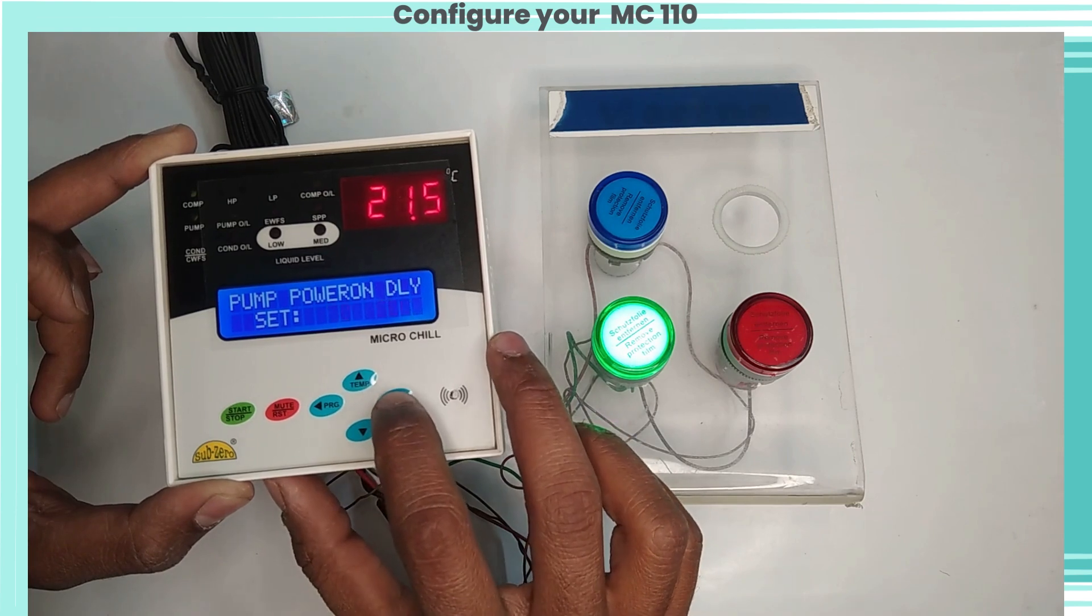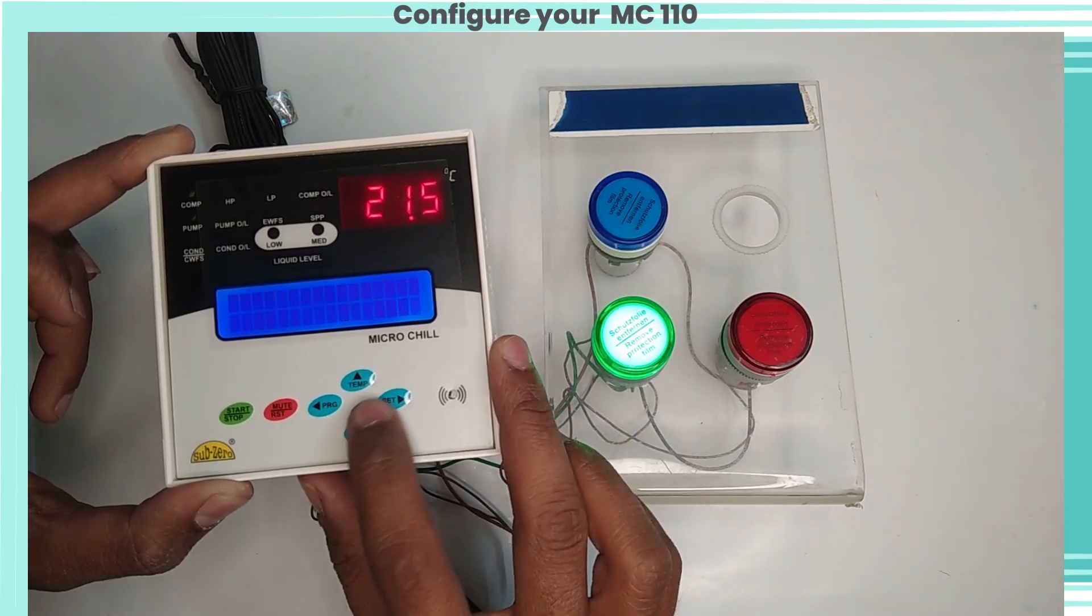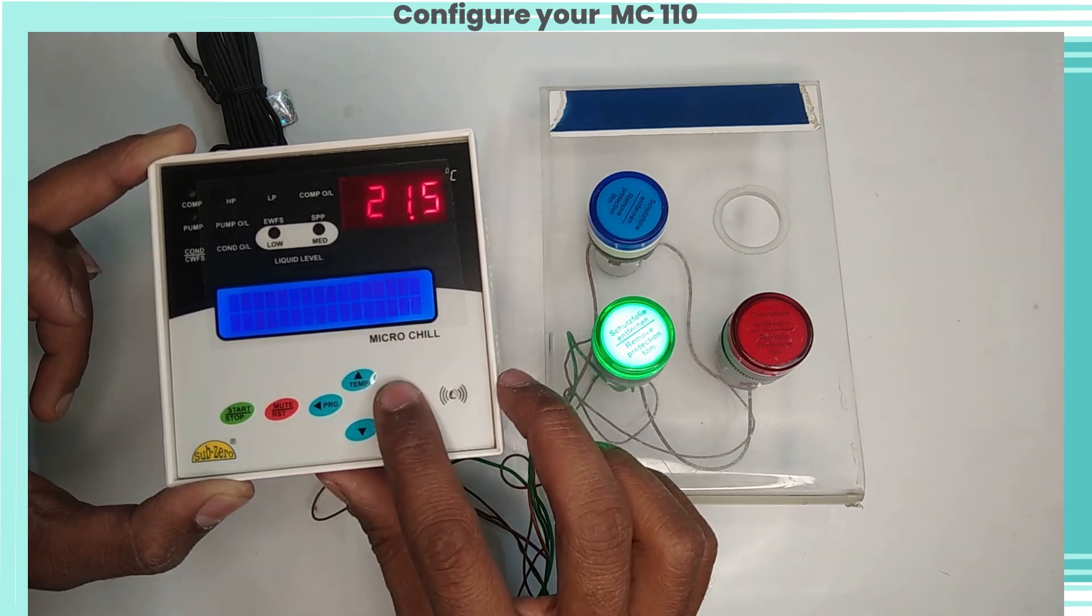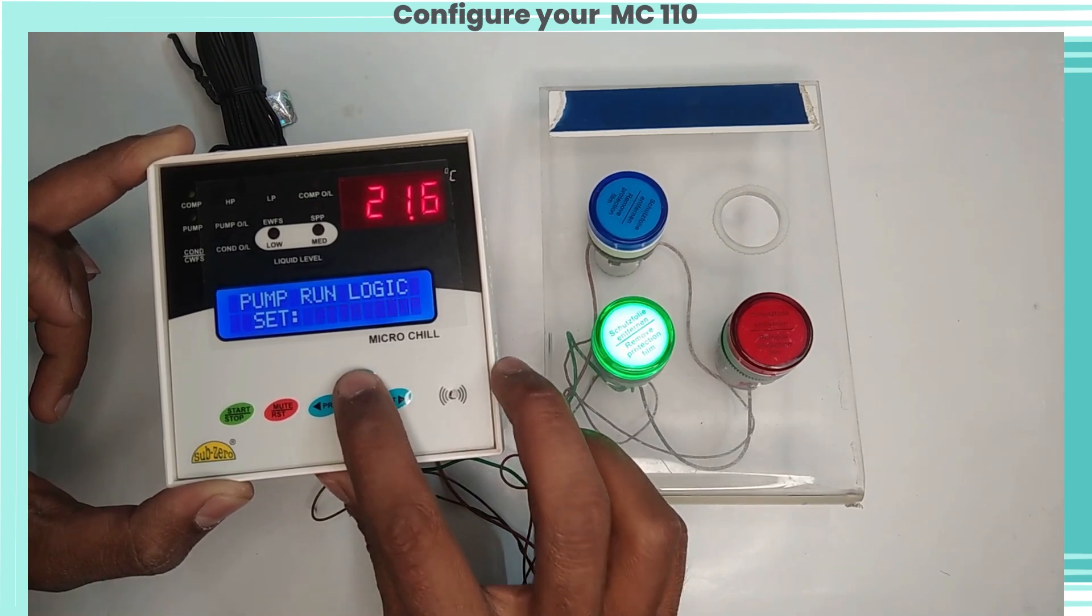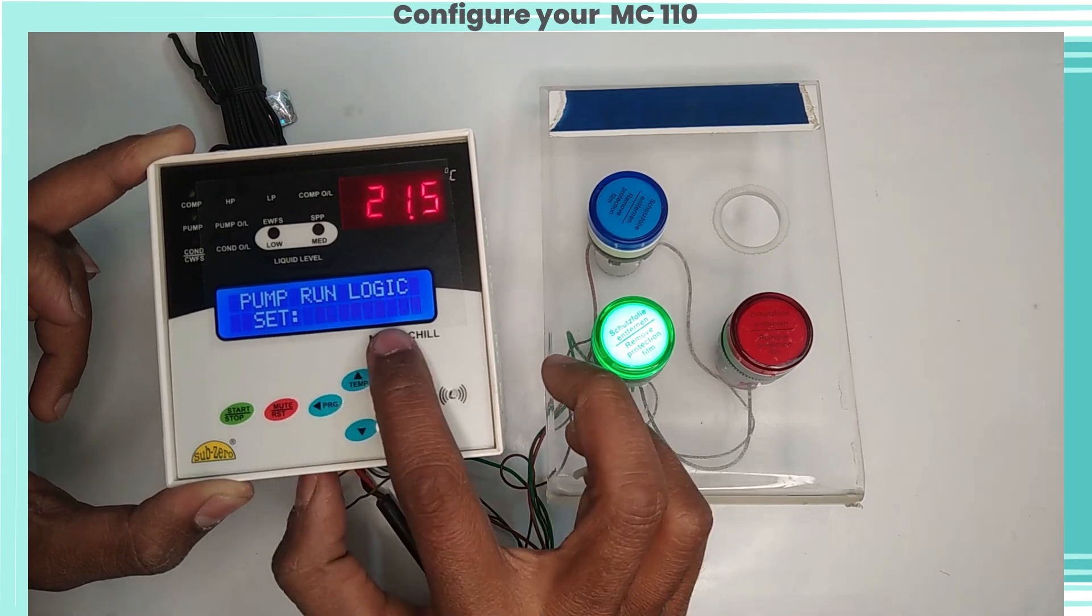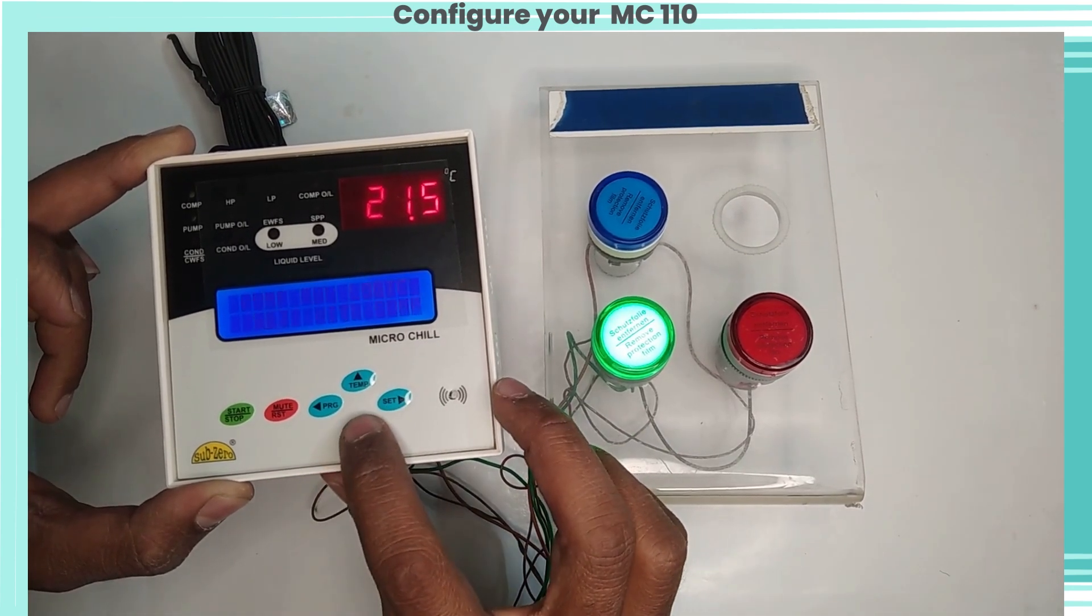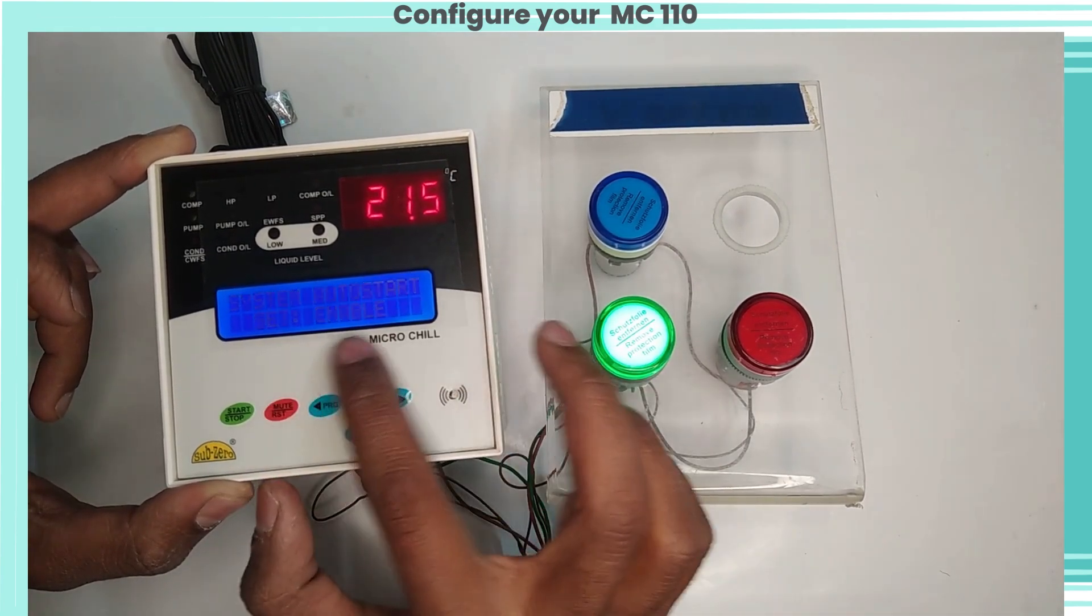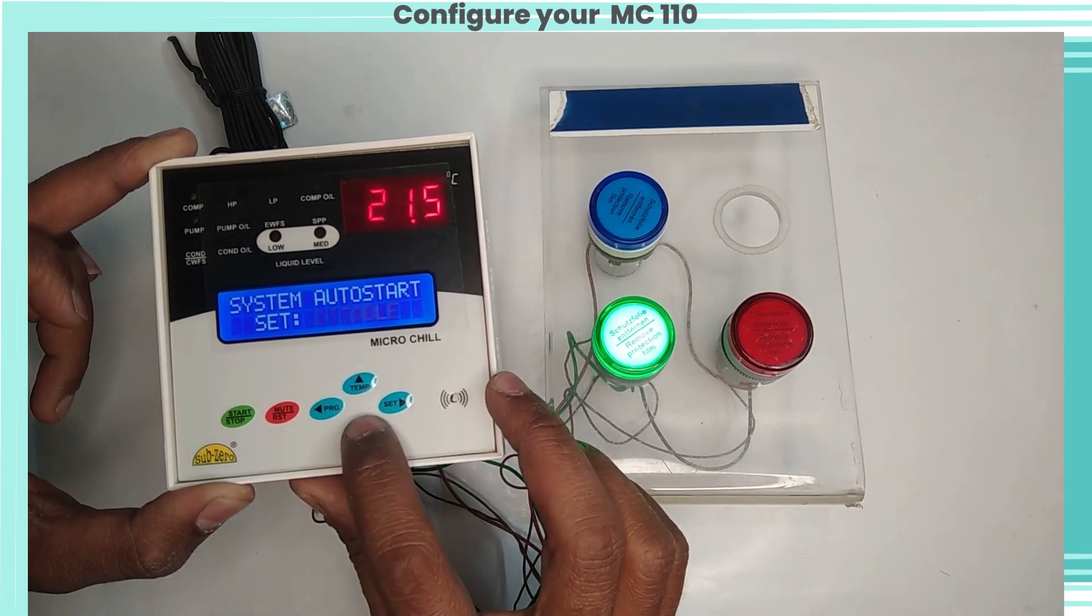Pump power on delay: this parameter is used to set delay for pump to start at power on. This is applicable if the pump is running with compressor. Pump run logic: this parameter configures pump to keep always on or off with compressor. System auto start: this parameter configures system to auto start or manual start on power on.